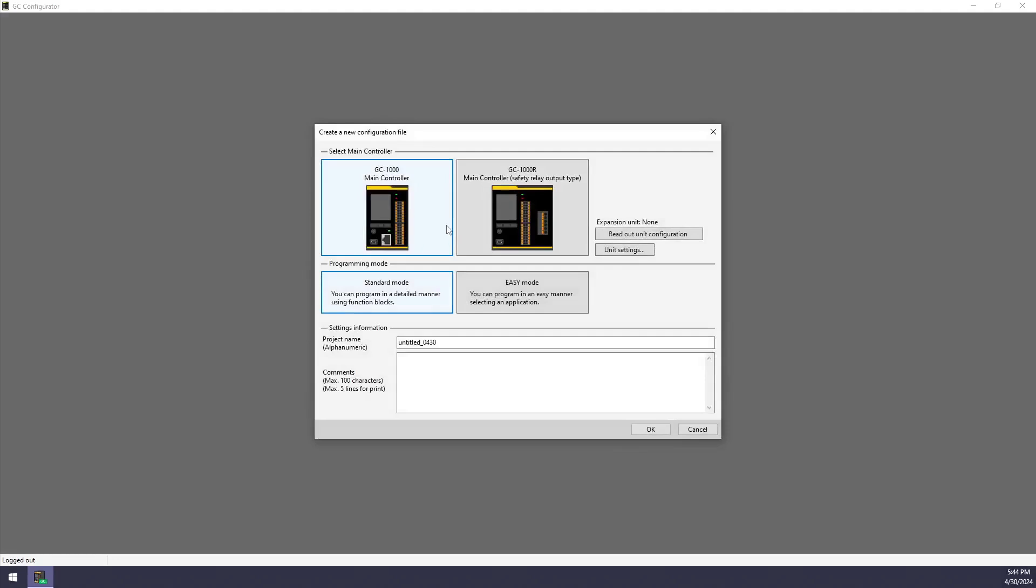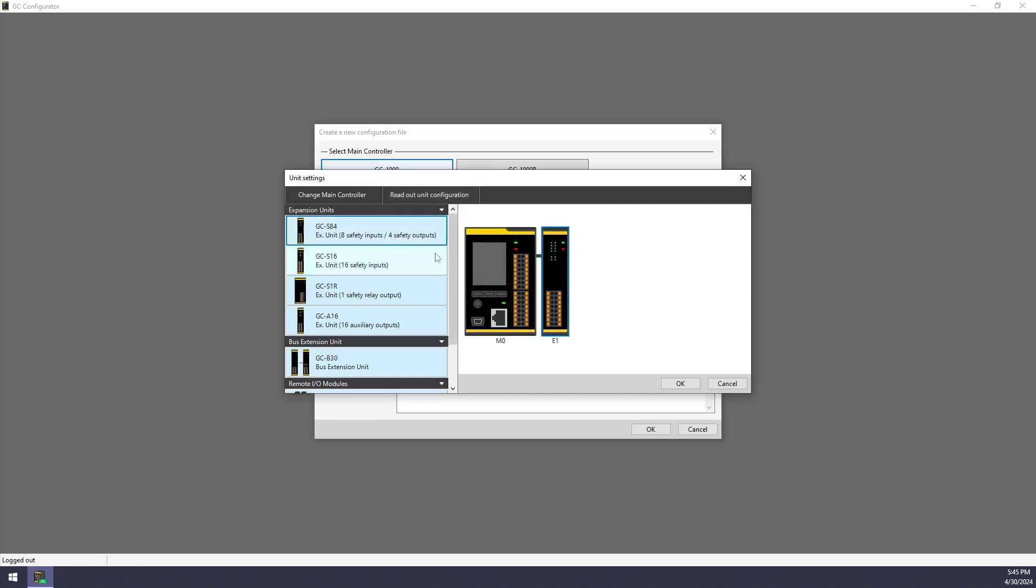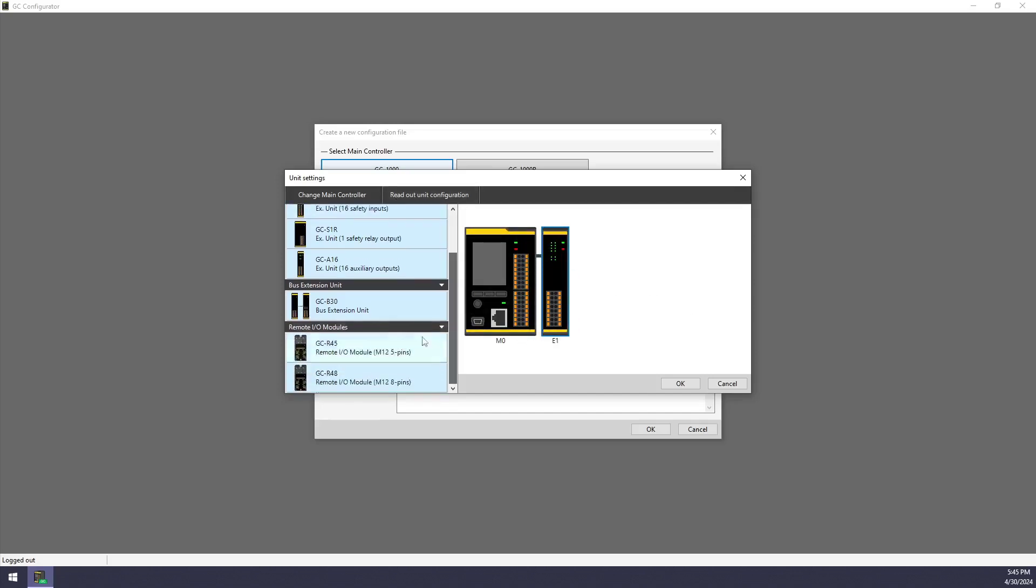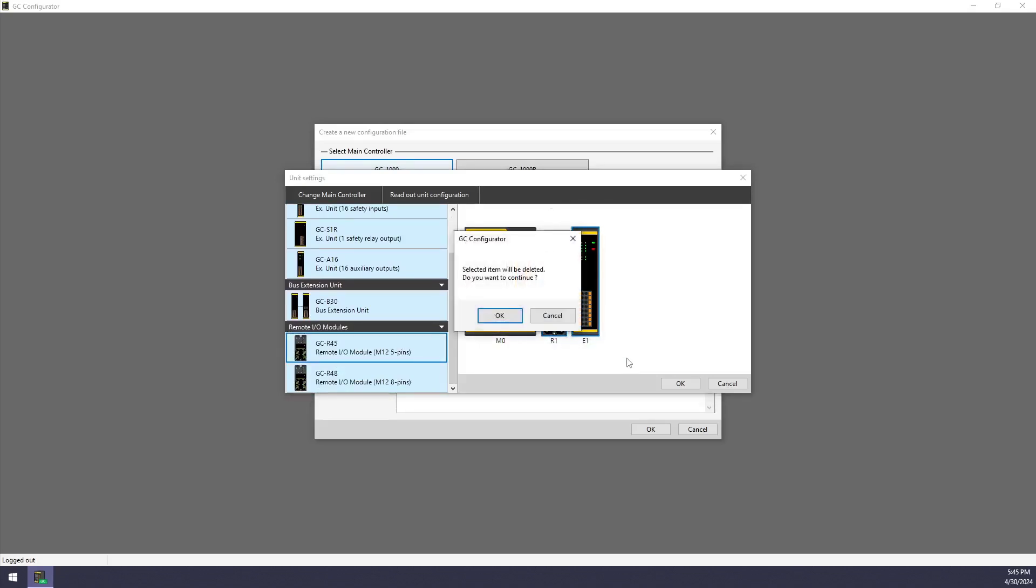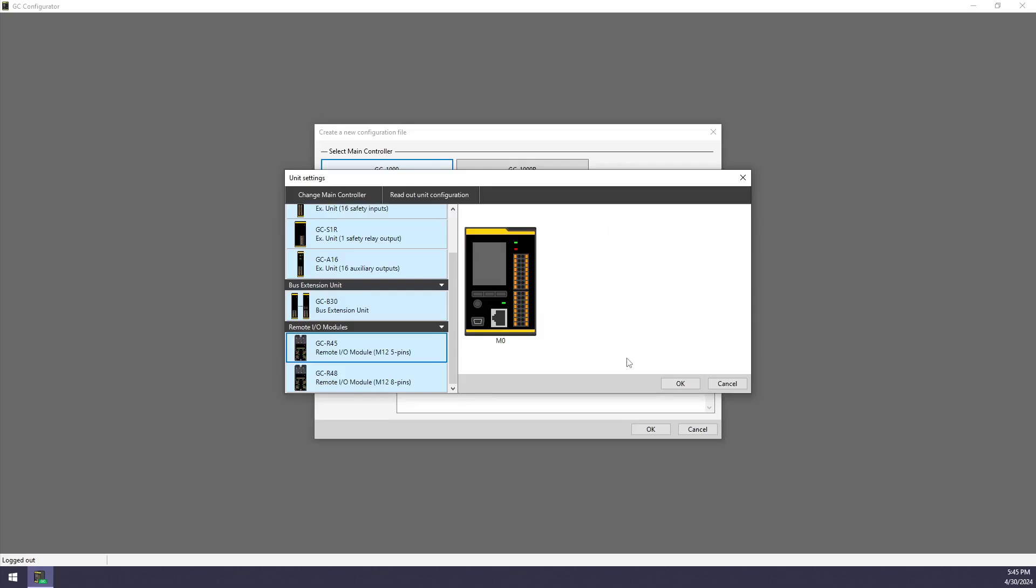This is a screen where I can identify the hardware that I'm going to be using. So I'm going to be using a GC1000, not the GC1000R. And if I have any expansion modules or remote I.O. modules connected, I can go into the unit settings. I can either read out everything if it is powered up and connected. Otherwise, I can manually configure what expansion units I'm using and what remote I.O. modules I'm using. Currently, I'm just going to pretend that I have none connected and I'll delete those out.